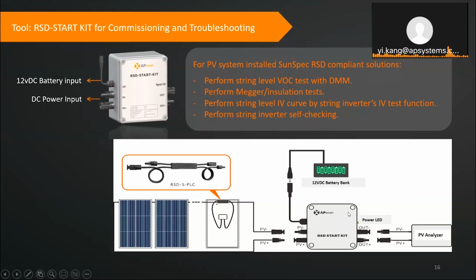One of the reasons we designed this tool is especially for commercial jobs. After you install very many strings, you need to make sure every connection is good. So later I will show you how to commission with this one. You can turn on your string and look at the output VOC level to confirm all the panels in your string turn on and function. And for large systems, you also can do a certain level of Megger testing. I think I did the testing on installations under 1,000 volts for commercial jobs.